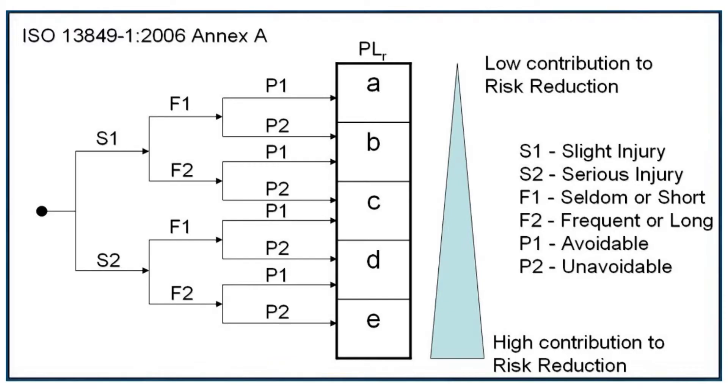So if anyone can put a body part into a point of operation, you must determine the risk to which they are exposed. Currently the international standards reference 150 Newtons or 15 kilograms, which is roughly 33 pounds of force or 33 pounds of mass, as the threshold at which additional safety measures must be taken in a system. For pneumatics, this corresponds to any cylinder that's really greater than one inch, and many that are just at the three-quarter inch size at typical plant pressures that we see.